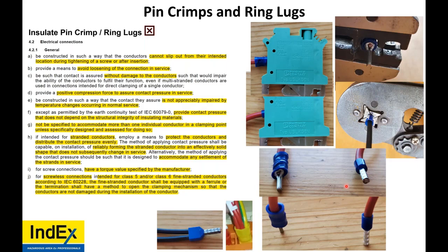Once again, in the standard, it clearly calls for ferrules or core end sleeves. Every single line by line here, reliably forming the stranded conductor into effective shape that does not subsequently change in service. It accommodates any settlement. Once again, it's misshapen and not perfectly formed in an insulated pin crimp. Have torque values specified by the manufacturer. Both of them have that if you use a proper crimper. But for screwless connections for fine strand wires, conductors shall be equipped with a ferrule, or a termination shall be made to open the clamping mechanism so that the conductors are not damaged during the installation of the conductor. Well, by using an insulated pin crimp, you are damaging the conductor and the insulation of the conductor and the insulation of the pin crimp.